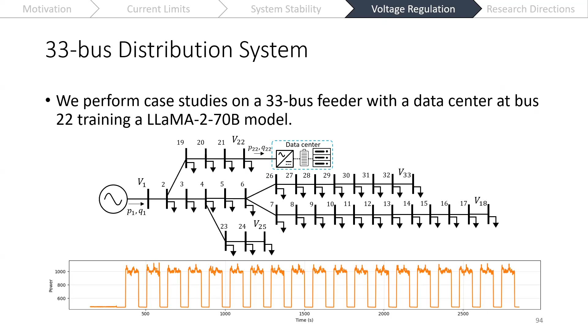We test this on a 33-bus distribution system, where we have a data center at bus 22, and we're running this large language model training load as shown below. Comparing to a fixed reference controller, which is just trying to drive the voltage to 1, we can see larger deviations in each step as it's trying to regulate the voltage to 1 before that step occurs. With the switching reference controller, after a bit of time, we converge such that the steps within our voltage are centered around 1, and we have better performance within the plus or minus 5% limit.